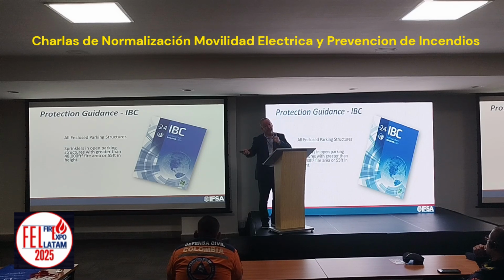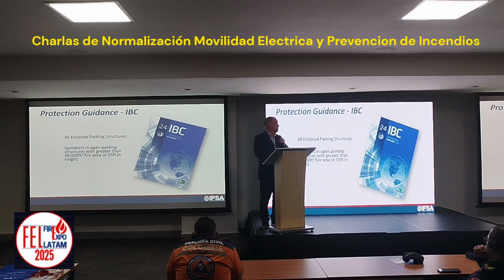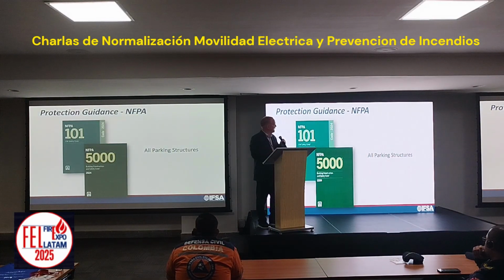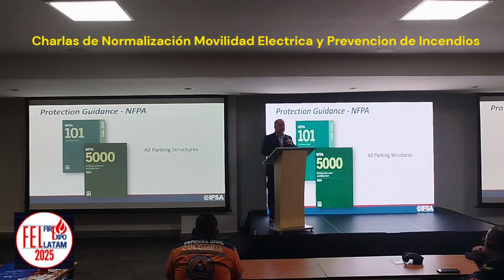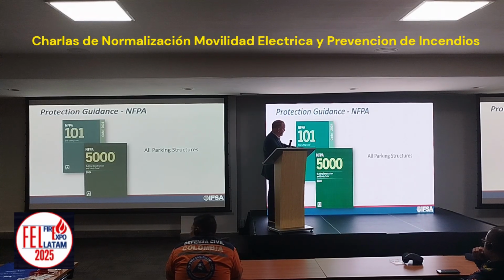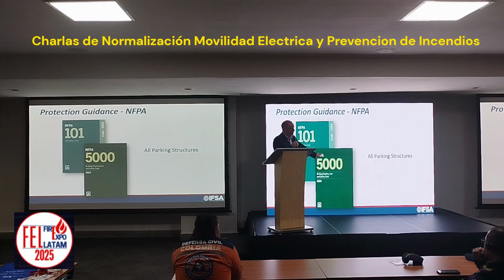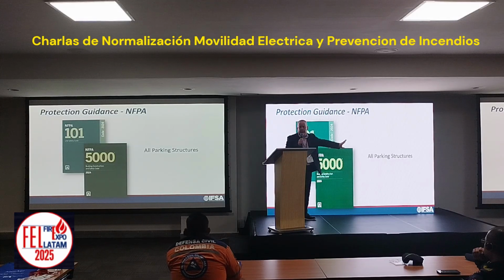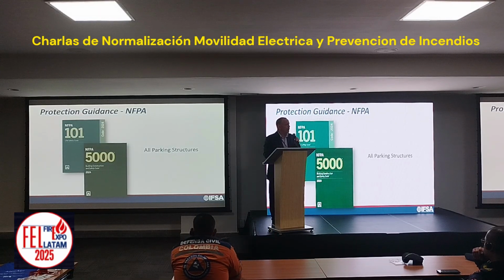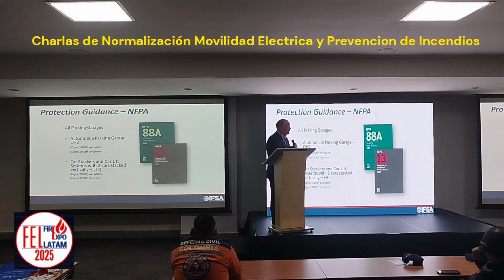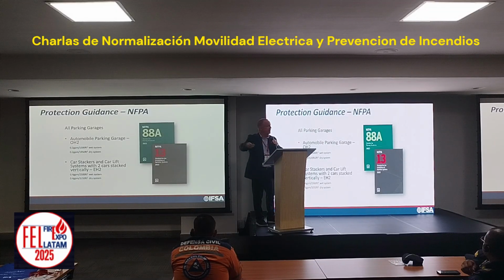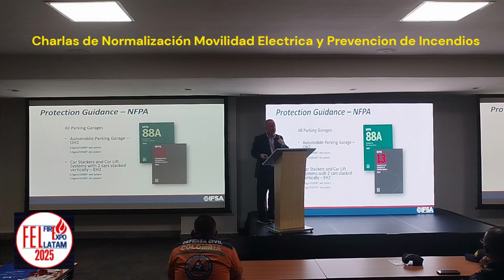Open parking structures with no sprinkler protection - now I'm loading them up with lithium-ion battery vehicles. Typically what happens is if we look at NFPA's side of things, the NFPA building code and life safety code both say all parking structures, regardless of whether open or enclosed, need to have a sprinkler system. Now you go to two other NFPA documents for further guidance. NFPA 88A is the standard for parking structures, and it says all parking garages also need to be protected.